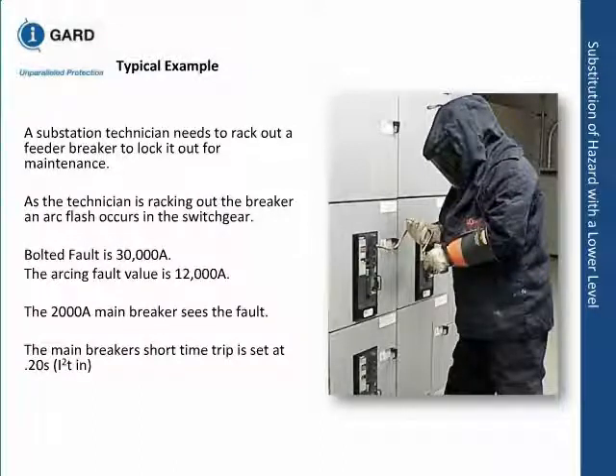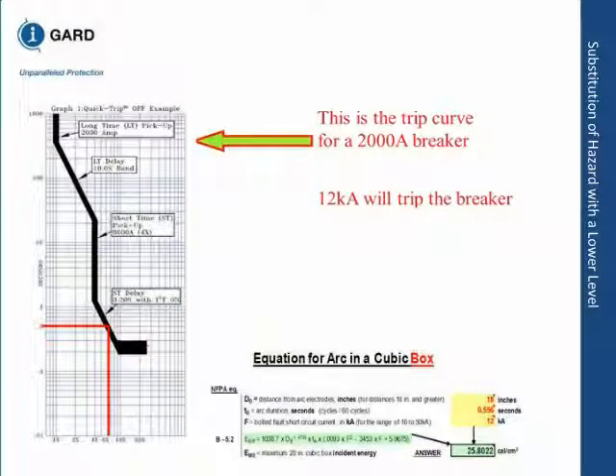When this person is racking it in, if the fault happens on the line side stabs or even on the load side stabs, it'll try to migrate to the line side, so the upstream breaker has to take it out. Now, in this slide, you can see how long it takes. Okay? 12,000 amps will trip the breaker. It takes about 0.5 seconds or something to that effect. If you calculate that arc flash, based on that time, you'll see about 25 calories. Even if that person has a suit on.